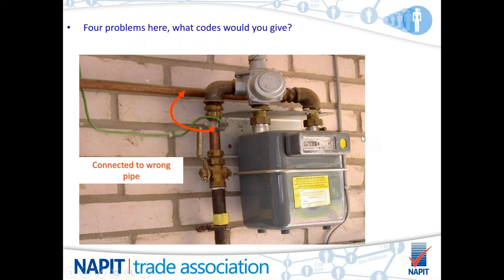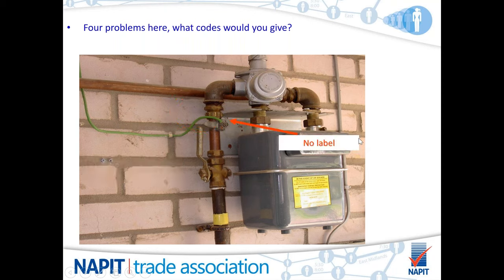The second one, no label on the BS 951 clamp. It wouldn't matter whether it was on the incoming service or on the installation pipe. There is no label. It does not comply to BS 7671, so maybe we could have your opinions on your codes here, please.